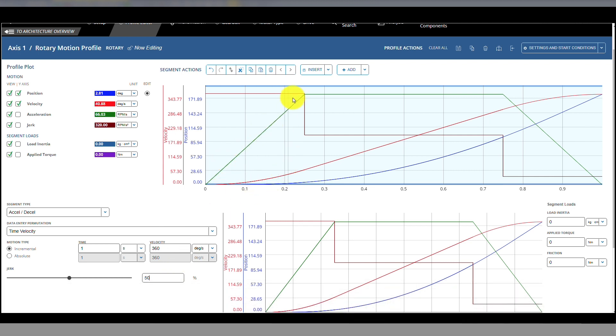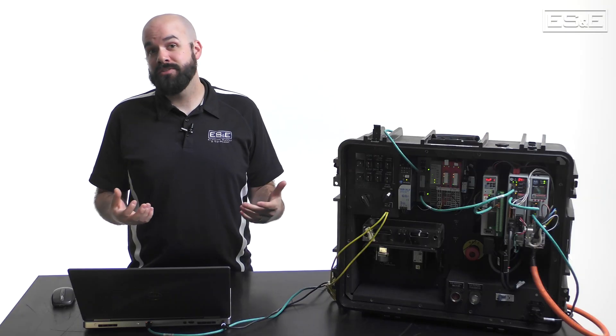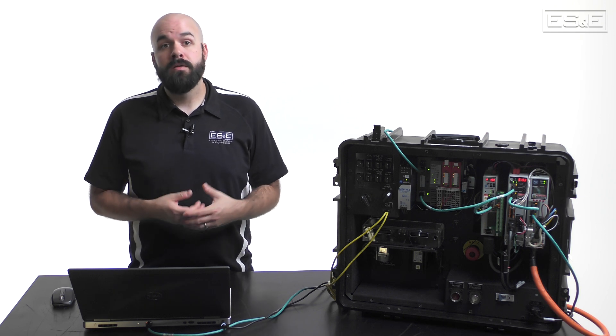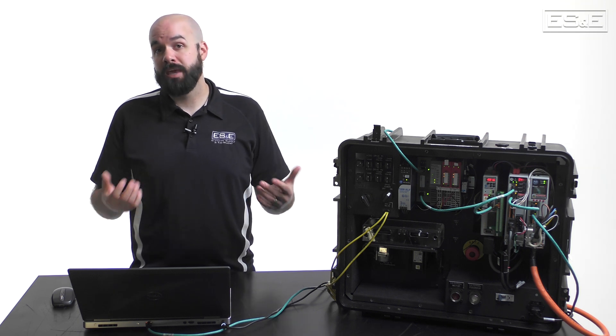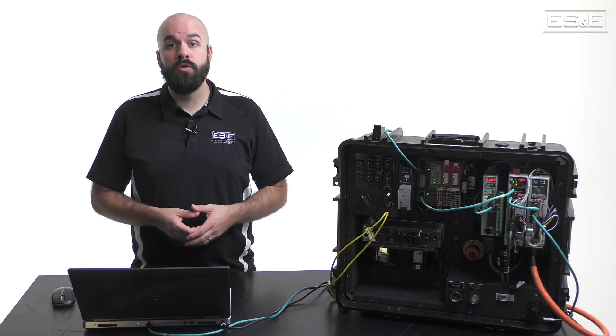If you would like to add an S-curve, simply apply a value in the jerk field. Entering 50% jerk means that the profile will use 50% of the move time to ramp the acceleration. However, with jerk set to 50% of time, we can see that the acceleration now needs to be set to 480 degrees per second squared in order to reach the target speed in the same amount of time. It's generally a good idea to use jerk in all your moves, as adding jerk — or S-curve as it's sometimes called — puts less wear and tear on the mechanical system and allows for greater control over the moves.